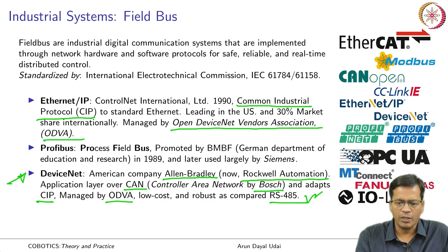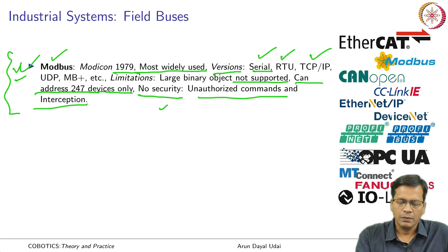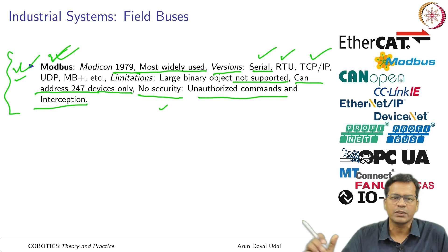Now comes Modbus. It was given by Modicon in 1979. Most widely used versions of Modbus are serial RTU, TCP/IP, UDP, Modbus Plus, etc. It has many limitations, like large binary format is not supported. So, that is the reason it can handle addresses up to 247 devices only, and it lacks security. Unauthorized commands can be given and interceptions cannot be checked. So, because of safety, security and limitations in its format, it is limited, but yes, still it is most widely used in the industry because of its simplicity. This protocol is very popular.